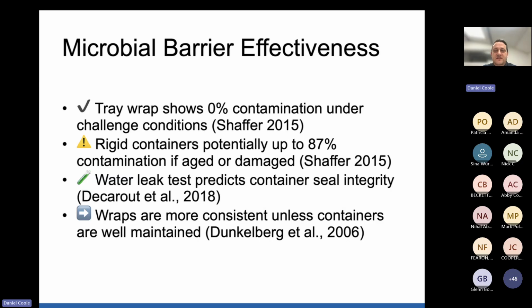A water leak test predicts container seal integrity, so that's something being used: a water test. And wraps are generally considered more consistent unless containers are well maintained. I'm going to show you some pictures later that challenge that and pose further questions. But I just want to reflect here on the testing. It's been highlighted that there is a concern around, once we seal a container, how do we know it's tested? Well, there are some new innovations out there, and I'm just going to share a short video of one of those for testing containers and the integrity of the seal.